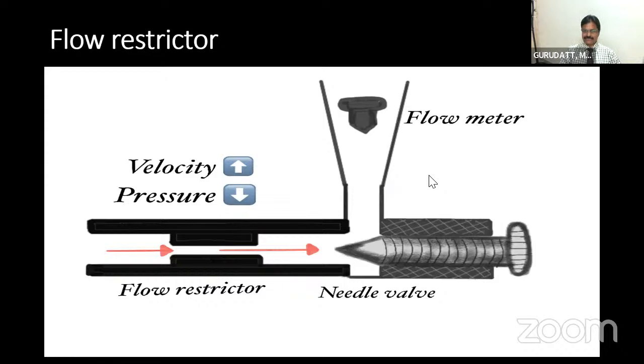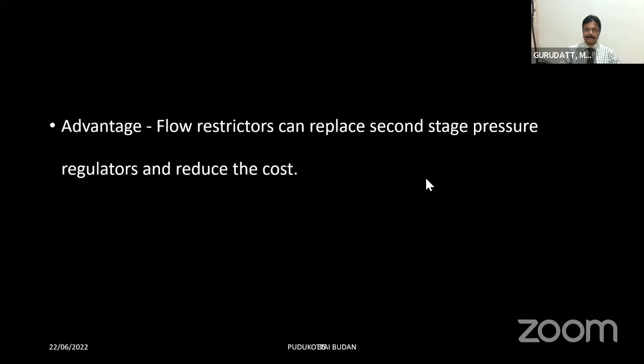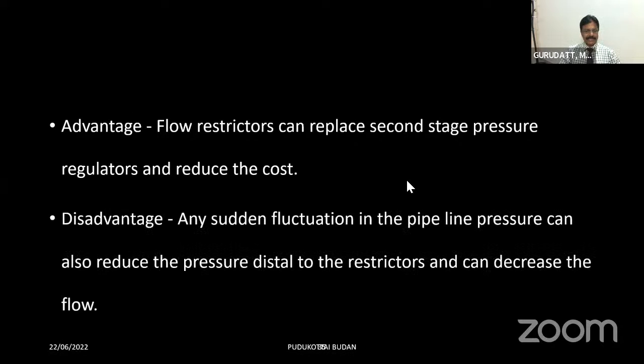The advantage of these flow restrictors in Draeger machines is that they have replaced the second stage pressure regulator, and also definitely they have reduced the cost. The second thing is you should also know that there is some amount of disadvantage because of the absence of the second stage pressure regulator, because any sudden fluctuation in the pipeline pressure can also reduce the pressure distal to the restrictors and can decrease the flow. That is always there with slight fluctuation of the pressures in the system. There can be slight alteration in the flow in Draeger machines, which is not there with the GE machines.